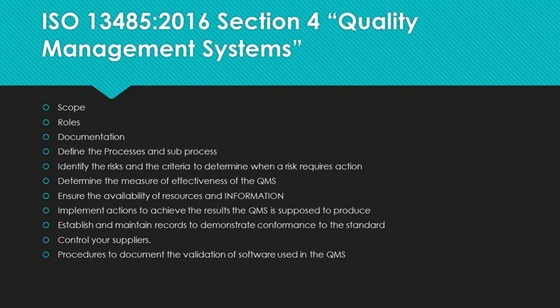And you must have procedures to document the validation of software used in the QMS. And software must be validated prior to initial use. Now, this is a new requirement for the 2016 revision, and there is some discussion among auditors as to what this means. Most auditors recognize that commercially available software, such as Microsoft Word or Excel, does not need to be validated, unless you are controlling the QMS using macros that you have written into one program or the other, in which case those will need to be validated.